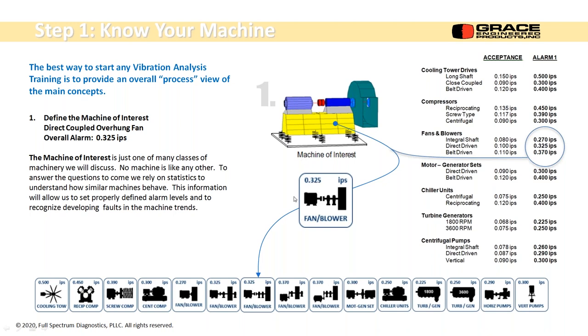And it's constantly comparing the data it's just accumulated to the allowable alarm level, which is this 0.325. This will change. This whole acceptance and alarm criteria is statistically set, but it's across industry. Your machine's different from every other machine on here. And each machine, I might have five of these fans all lined together. They're all different. They're all going to have their own alarm criteria. They're all going to have different levels of vibration.